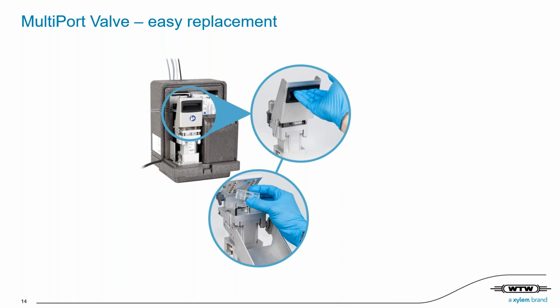Designed as the main spare part of the new analyzer, it guarantees always reliable and extremely accurate measurement values without any wear-out effects. Thanks to its long lifetime, it will need to be replaced only once per year. Located in the wet chemical unit, the MultiPort valve is installed in a special holder. Always having ease of use in mind, the holder was designed for easy access and replacement of the MPV, as shown here. Just empty the system, open the holder, replace the old MPV by a new one, close the holder, start the system, and that's it.